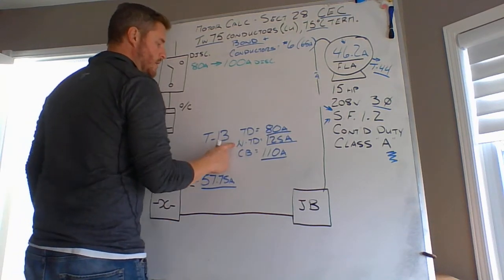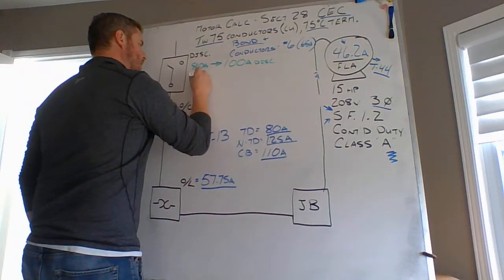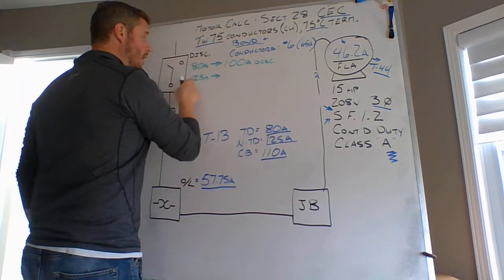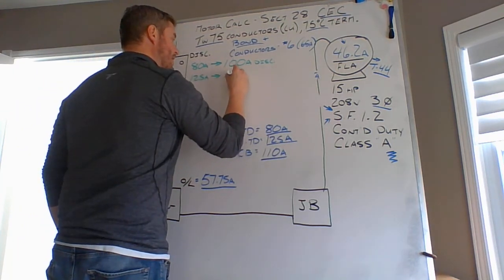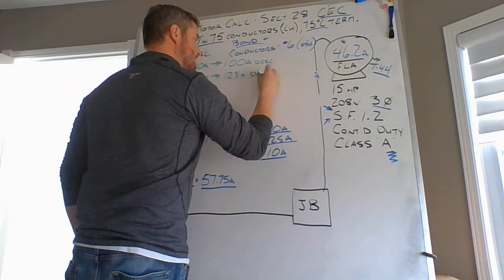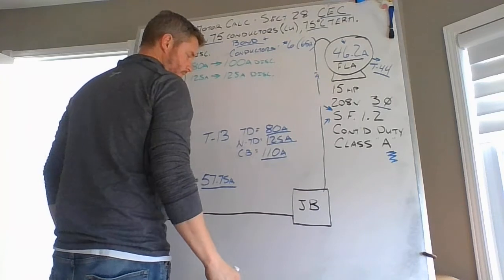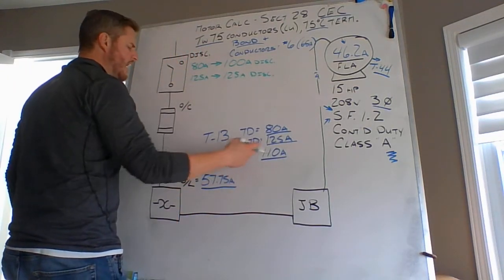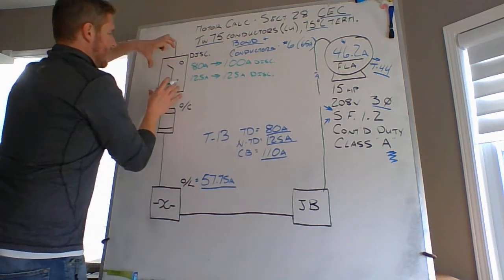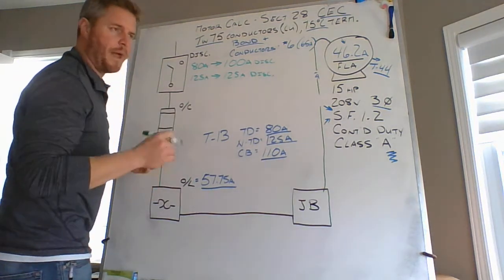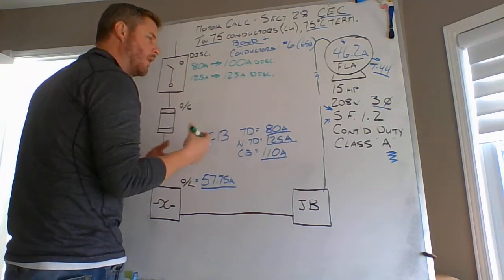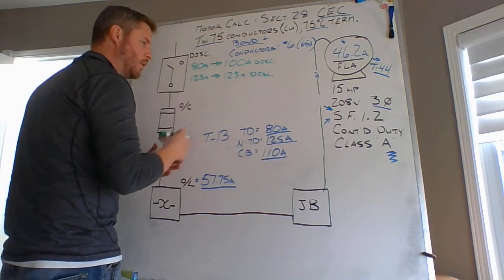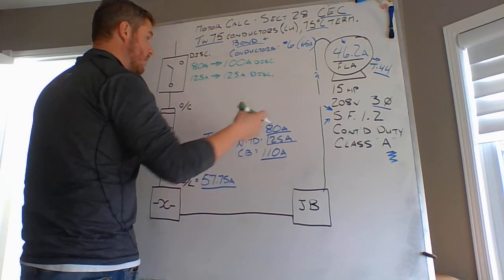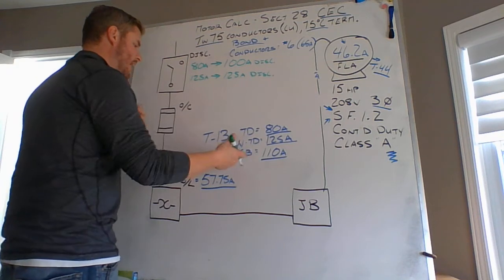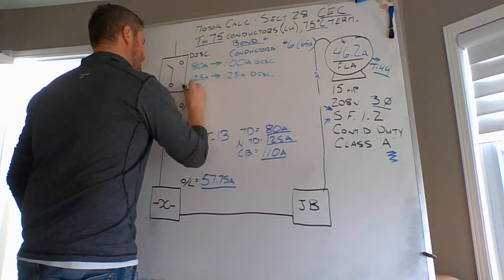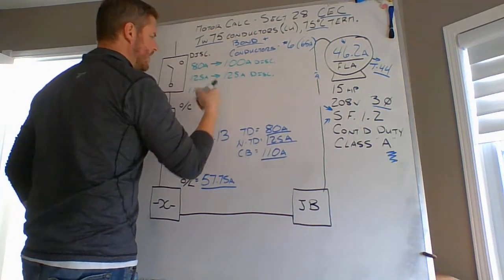Okay. If I chose non-time delay fuses, they're 125 amps, which means I can actually install a 125 amp fuse into a 125 amp disconnect. Okay. If I chose a circuit breaker, this disconnect might turn into something more like a spa pack. Okay, a spa pack meaning, like an exterior panel and how you hook up like a hot tub or a very small panel that you can put remotely somewhere else in a factory, for your installation of set of 15 horsepower 208 three-phase motor. And at that point in time, a 110 amp overcurrent device, that's fine. And that's going to go into your panel.